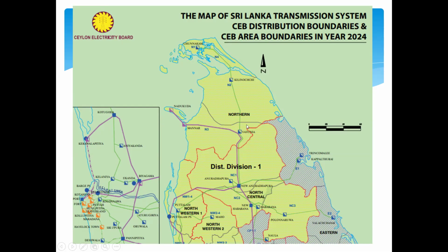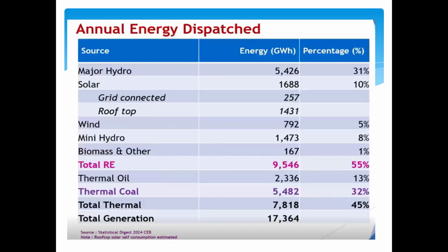If that tripped, the power transmission up to Chunnakam, Jaffna area, Kilinochchi, the northern part of the country, would be disrupted. So a major solar producer was switched off during that time in order to avoid feeder tripping due to the overload condition. If we consider the 2024 statistical digest of CEB, you can see the power produced from major hydro is 31%, but solar has come up to 10%, one third of that.